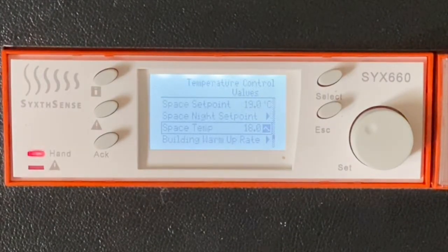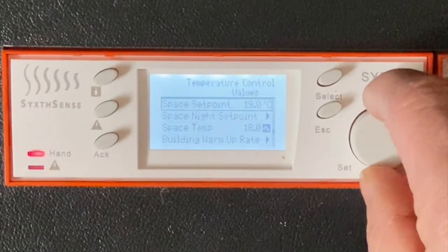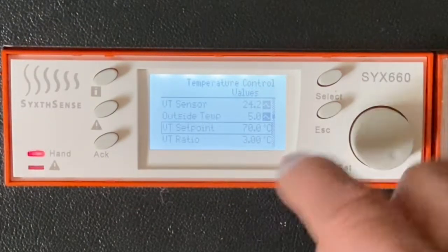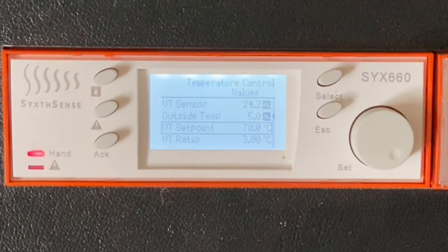Now that means that the controller will think it's a very cold day, and it thinks it's cold in the room, and it will mean that the heating will come on, and it will try to achieve a set point of around about 70 degrees, depending upon what the current room temperature is. There you go, flow set point 70 degrees, and then we can see the valve modulate, we should see the boilers come on, we should start to see the controller start to control the flow temperature around 70 degrees. And that's a good way of proving that that particular circuit is then going to be fed with the flow temperature we expect into that particular zone of the building.